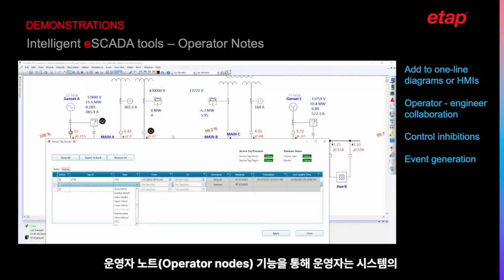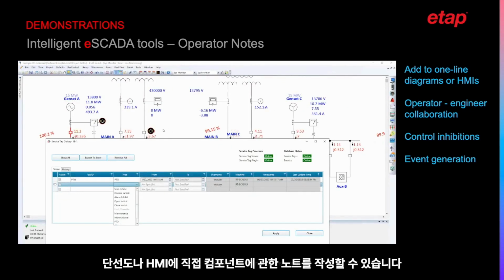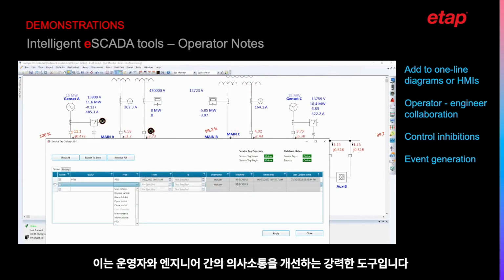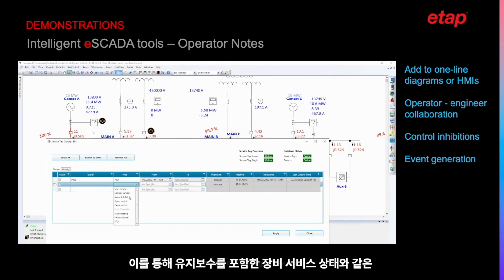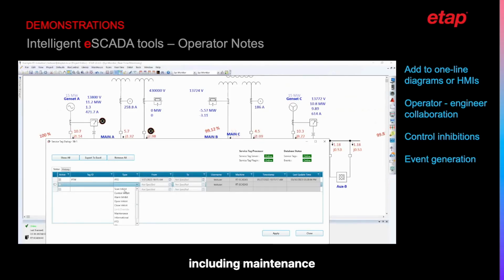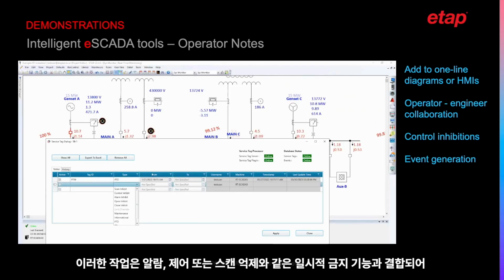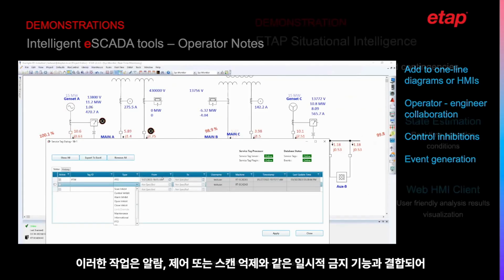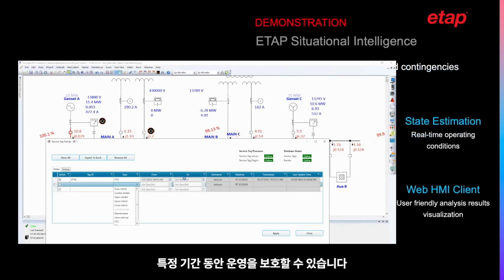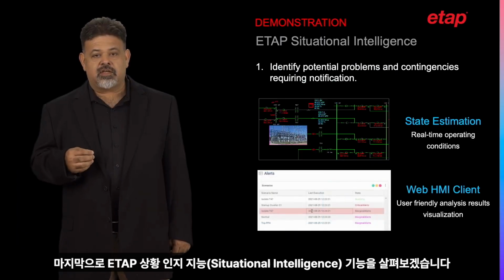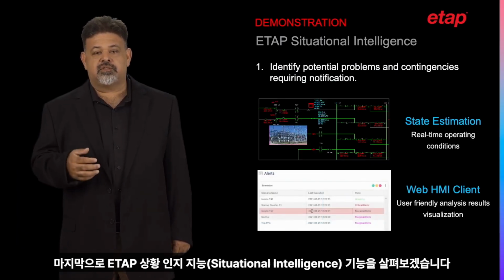Operator Notes allows the operator to create notes regarding components directly in the one-line diagram or HMI in the system. This is a powerful tool that can be used to improve communication between operators and engineers. It allows them to share important knowledge such as equipment service states, including maintenance. These actions can be paired with temporary inhibitions such as alarms, control, or scan inhibits to protect the operation for a specific period. Finally, let's take a look at the ETAP Situational Intelligence feature.